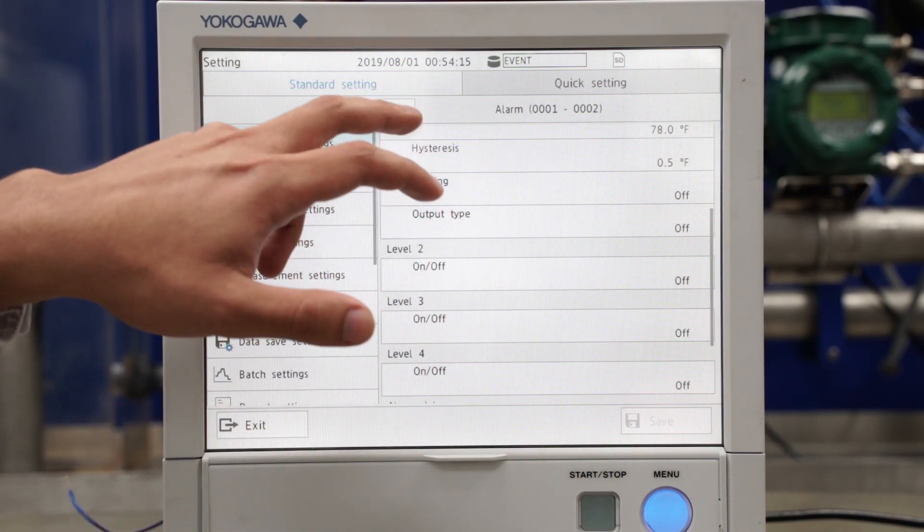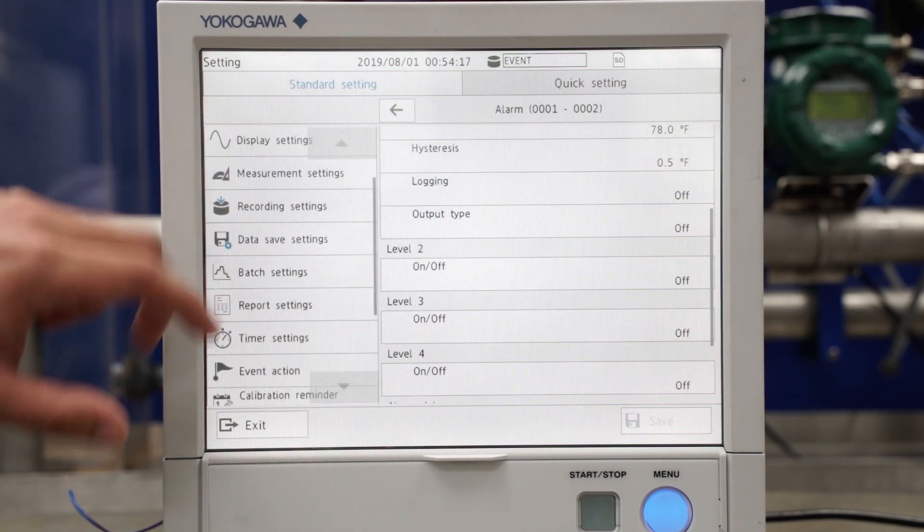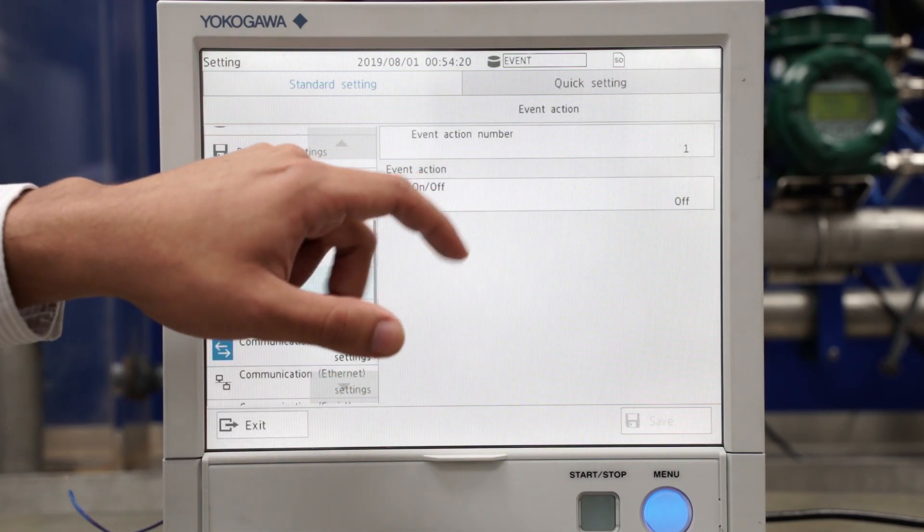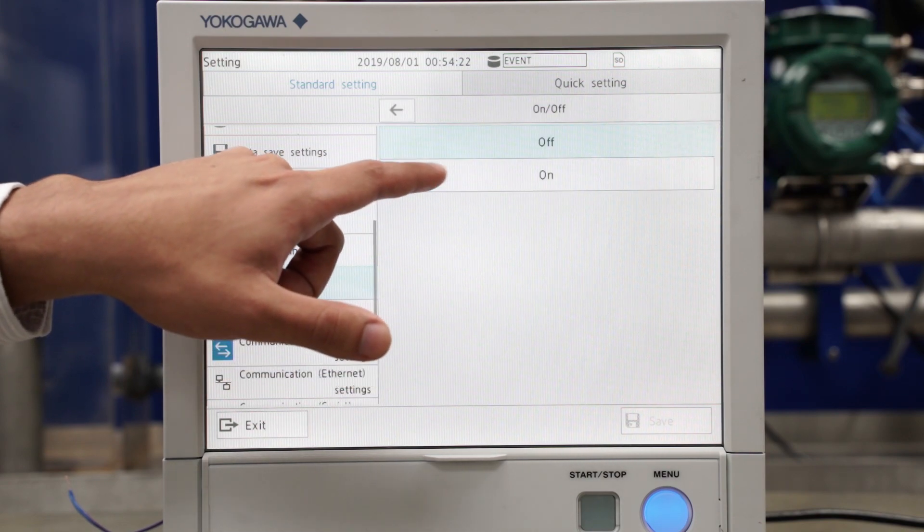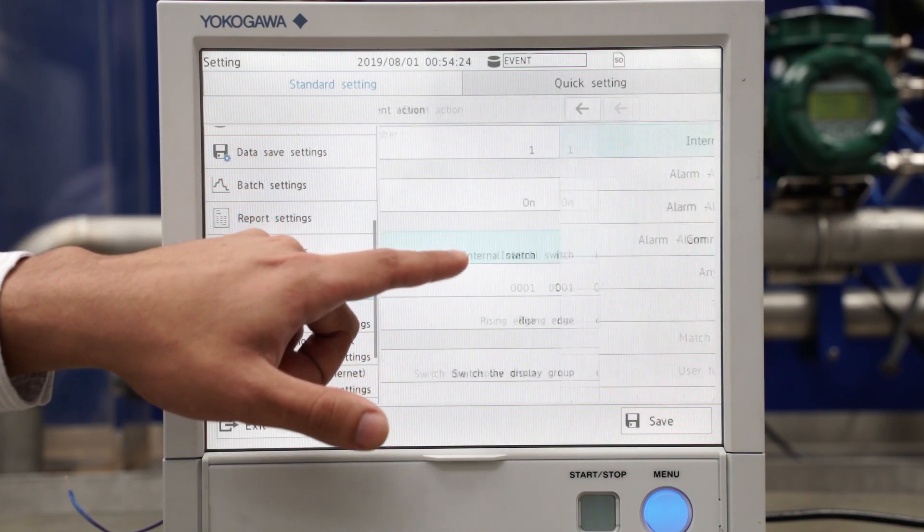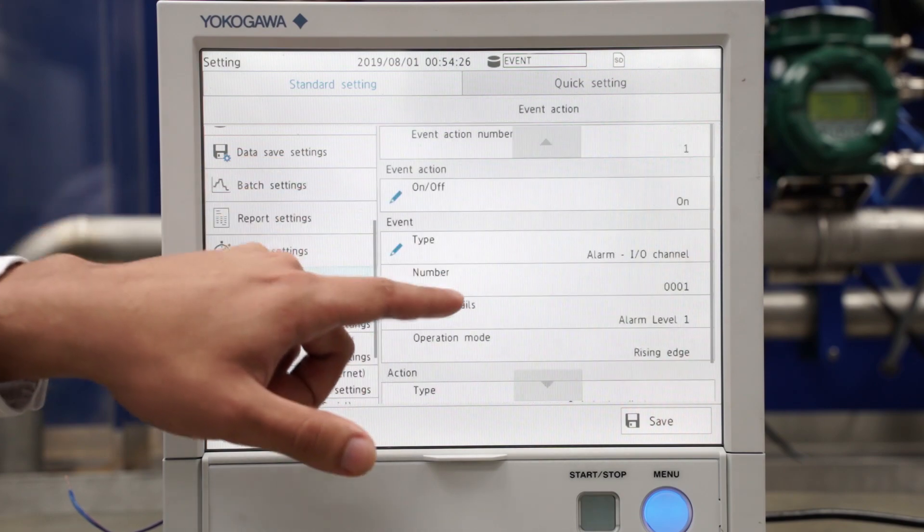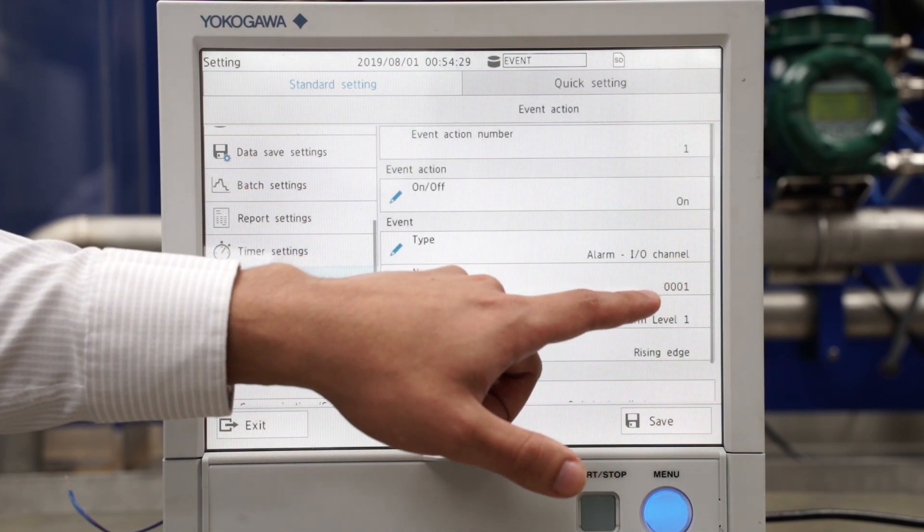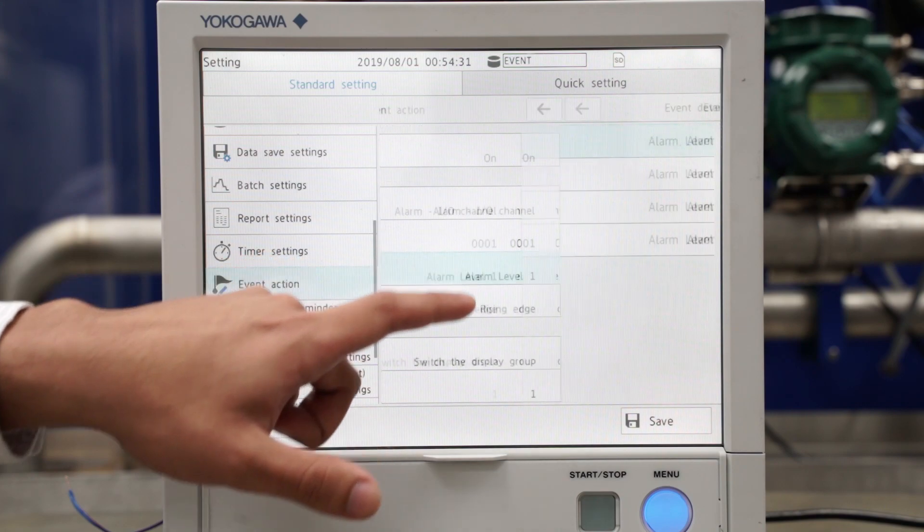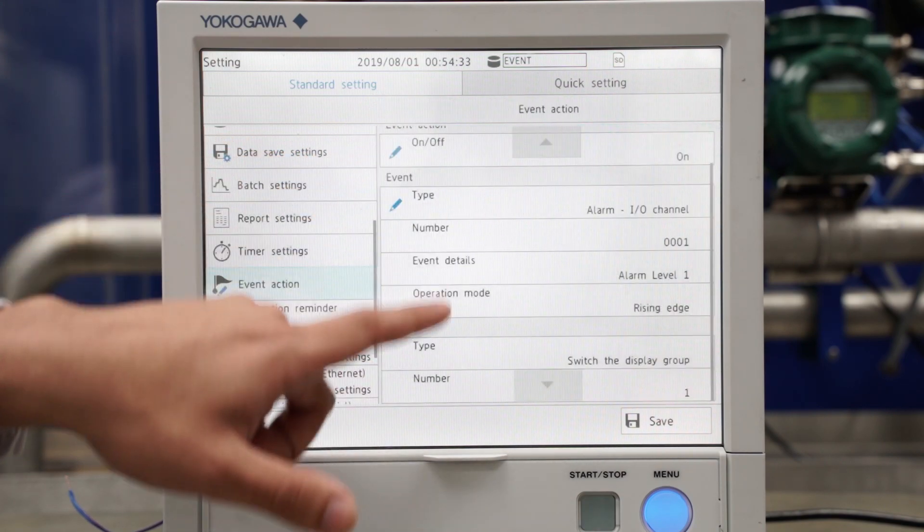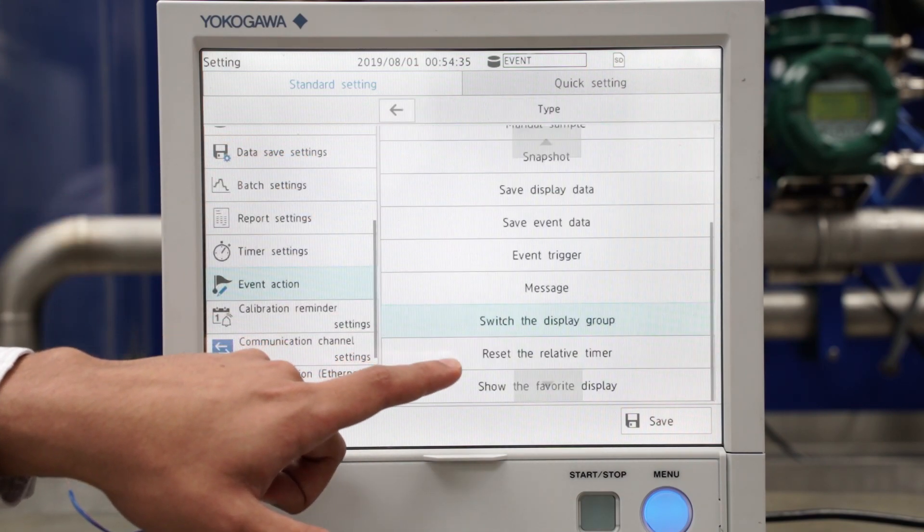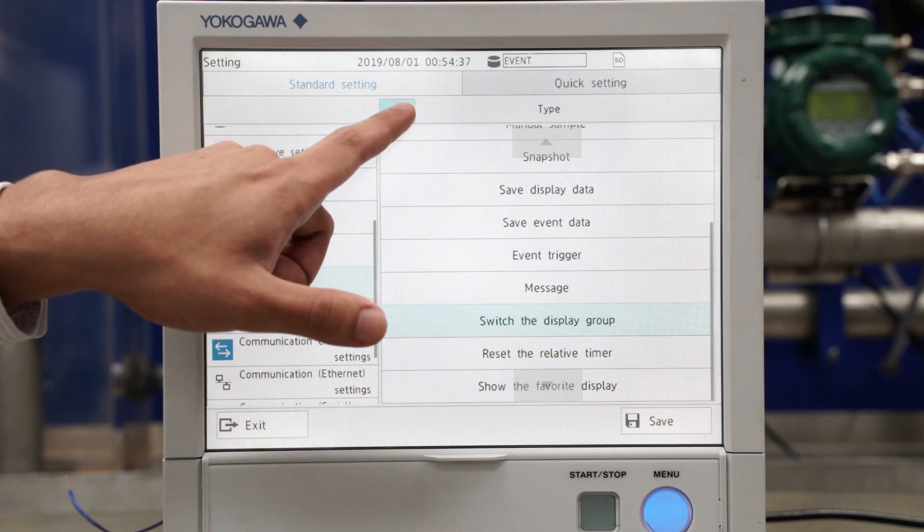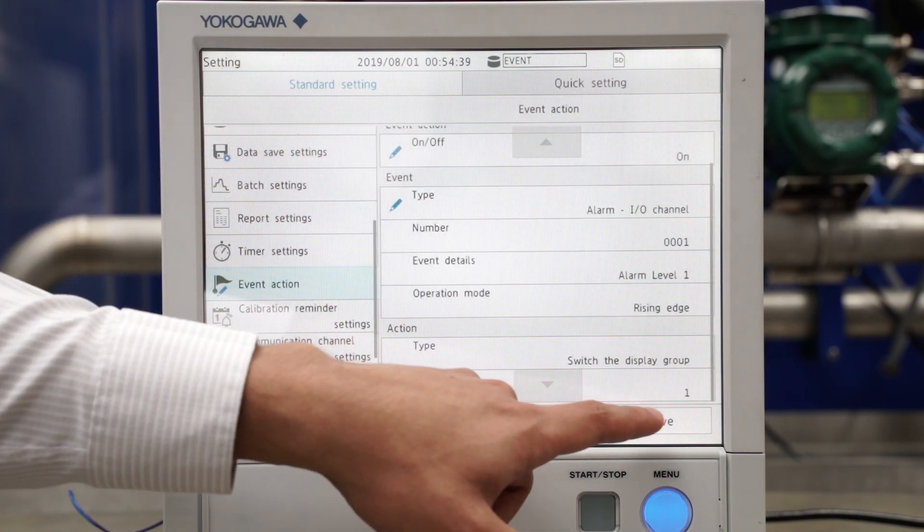And now I go to event action, event action number one. I'll turn that one on and I'll have that type be an alarm, and it will be the alarm for channel one. The type of action I'll have is switch the display group to group number one. I'll save that.